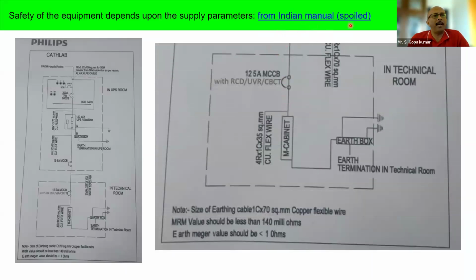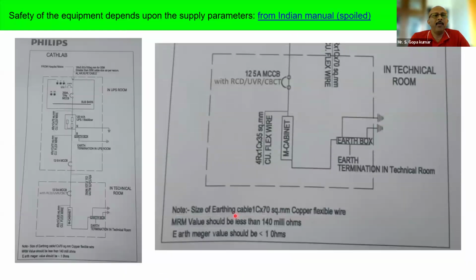I have put it as spoiled. I am showing the name of the manufacturer purposely because, as you know, we were trying to indirectly tell the manufacturers that because of your mistakes, equipment are in trouble, but most of the time they don't care. So you see here in the previous one, you can be sure that the equipment manufacturer has very clearly explained what the hospital or what the user should do. And here also they have explained what the user should do, but totally in a wrong way.